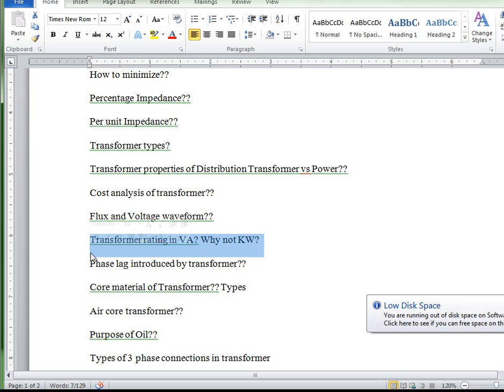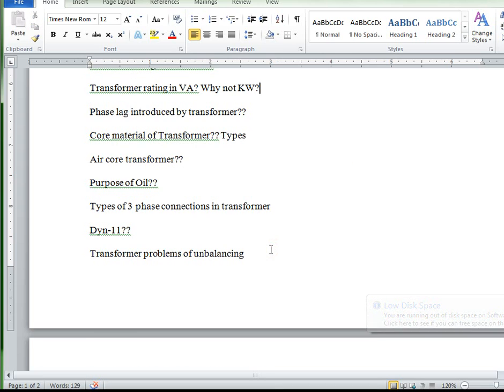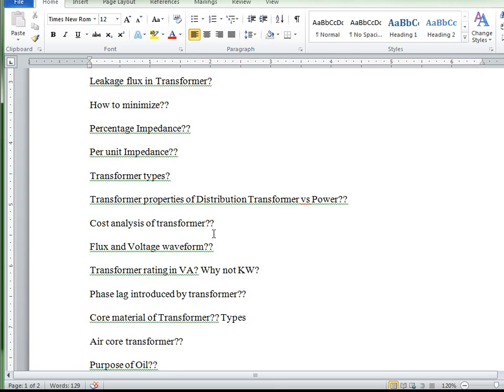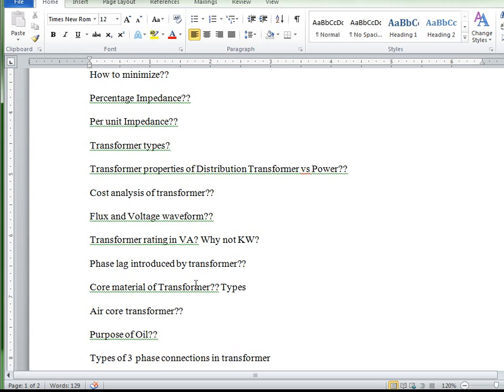A transformer is basically a series device which takes power from one level and converts it into another level. So the load has P demand as well as Q demand, and that has to travel through the transformer. So the transformer has to supply P as well as Q. That's why it's always rated as VA, kVA or MVA, and not rated in kilowatts or anything like that. Please kindly go through this, there are some questions over there.